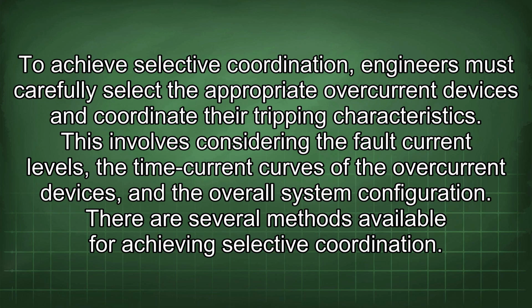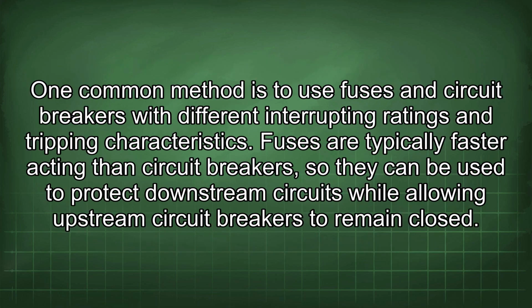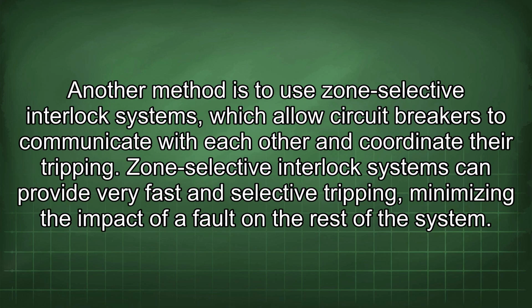There are several methods available for achieving selective coordination. One common method is to use fuses and circuit breakers with different interrupting ratings and tripping characteristics. Fuses are typically faster acting than circuit breakers, so they can be used to protect downstream circuits while allowing upstream circuit breakers to remain closed. Another method is to use zone-selective interlock systems, which allow circuit breakers to communicate with each other and coordinate their tripping. Zone-selective interlock systems can provide very fast and selective tripping, minimizing the impact of a fault on the rest of the system.